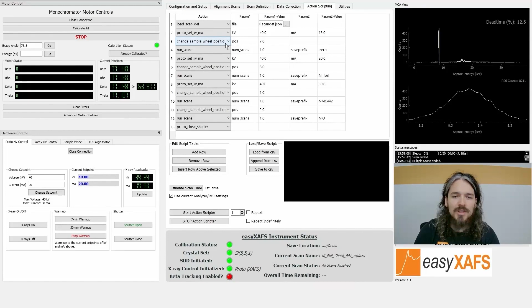Now that we're ready to set up the demonstration measurements, we can switch over to the action scripting tab. This is the system that we have for doing a sequence of actions. For example, we can load a scan definition, we can change the X-ray power settings depending on the sample, we can change the sample wheel position, and then we can run a number of scans. Here we have it set up.